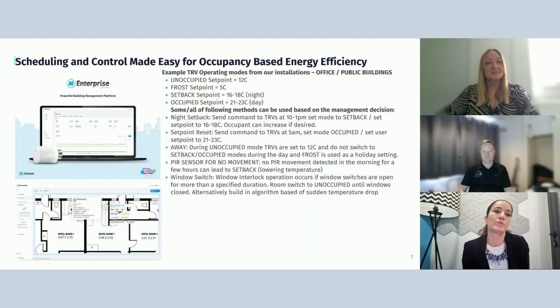Here's a simple example of occupancy-based energy efficiency. In most cases, the BMS gives you one kind of overview, but with the TRVs in particular on the radiators, you can use different set points and different schedules for every single day of the week, and depending on the time and occupancy, have different ways to play it out - for example, an unoccupied or empty building setting of 12 degrees.